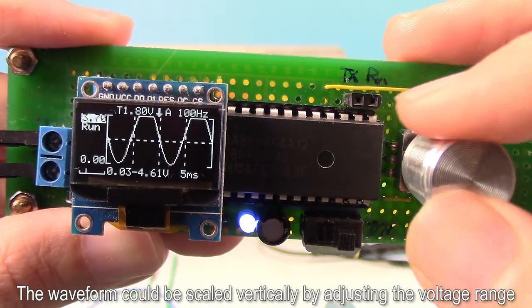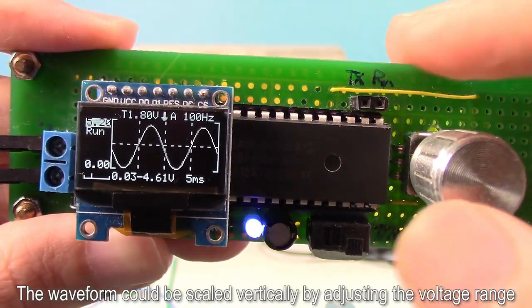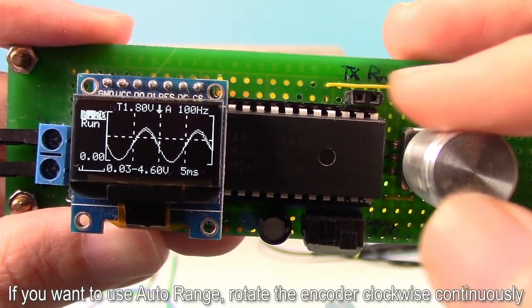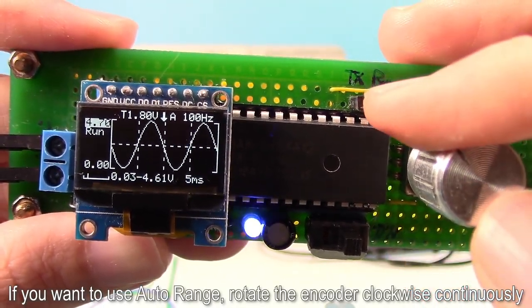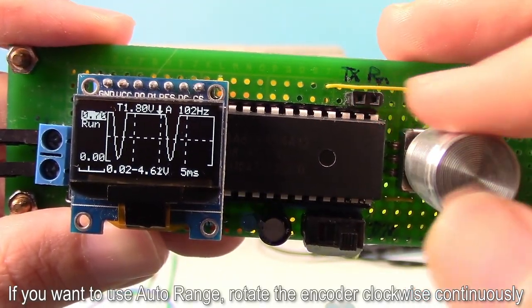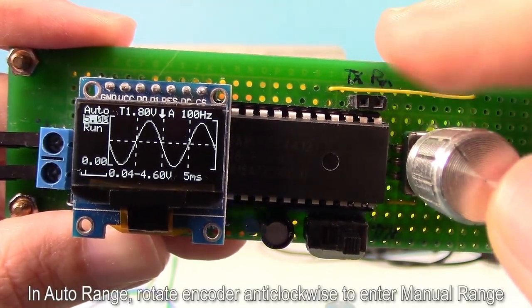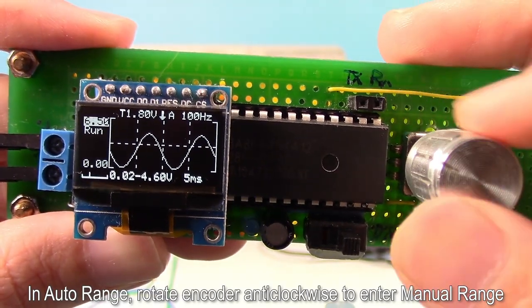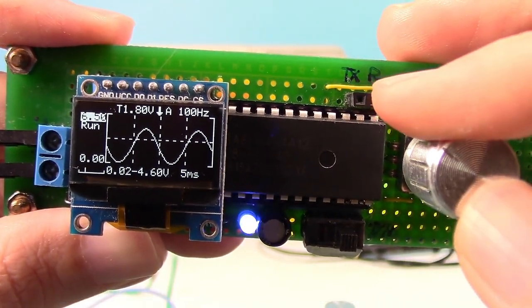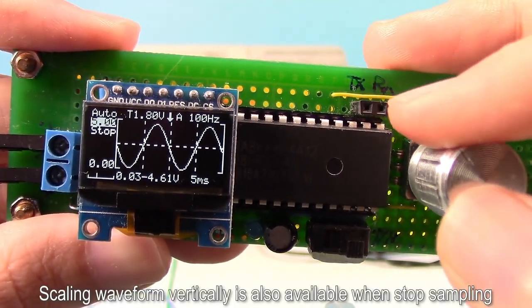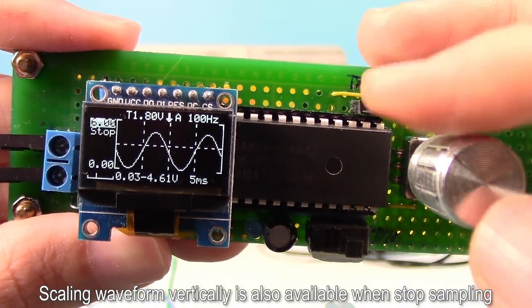The waveform could be scaled vertically by adjusting the voltage range. If you want to use auto range, rotate the encoder clockwise continuously. You will enter the auto range. In auto range, rotate the encoder anticlockwise to enter manual range. Scaling waveform vertically is also available when stop sampling.